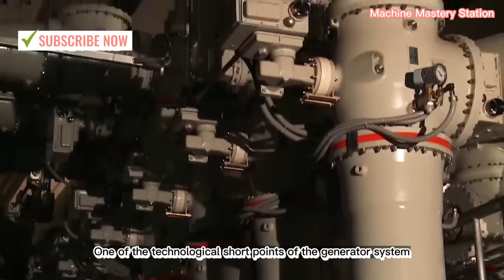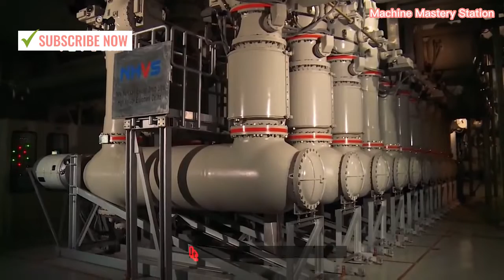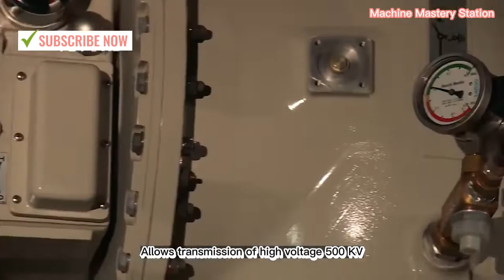One of the technological highlights of the generator transmission system being applied at Son La hydropower plant is the GIS system, which can be easily understood as a closed switching system that allows transmission of high voltage 500 kV to operate in a small space.